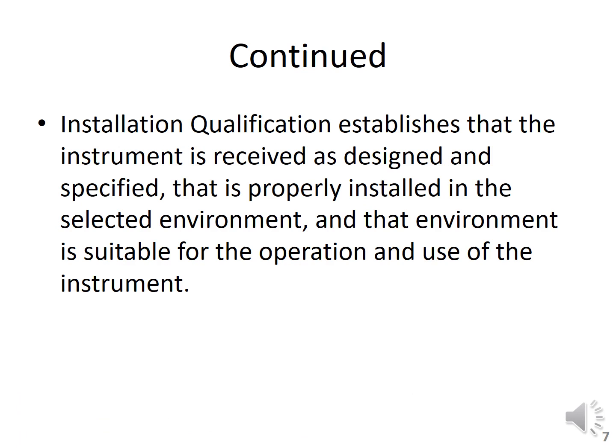Now, this is the continuation of the previous slide, right? Installation qualification establishes that the instrument is received as designed. We have discussed, right? And specified. That it is properly installed in the selected environment. The environment should be selected carefully, and then the installation should be done properly. So you have to check this point as well, and that the environment is suitable for the operation and use of the machine.